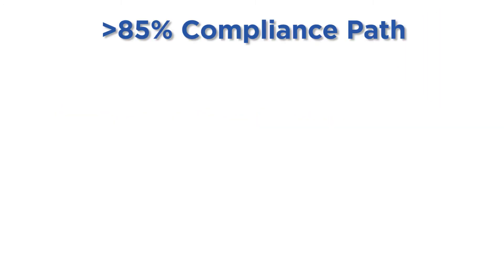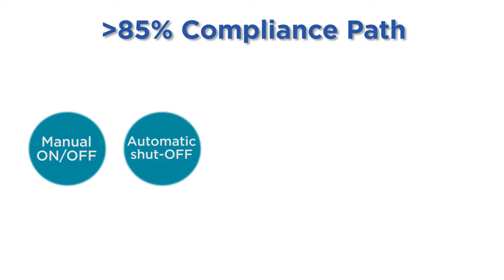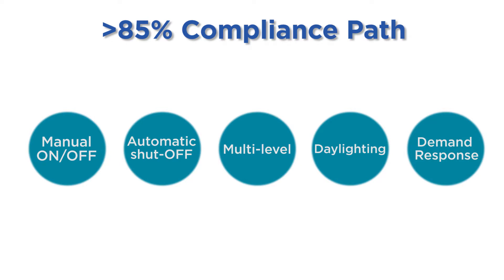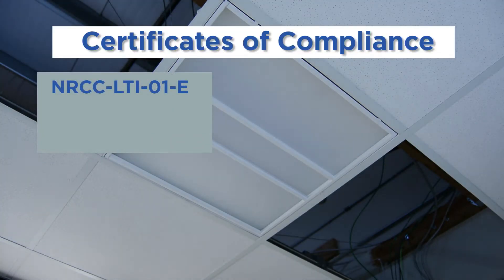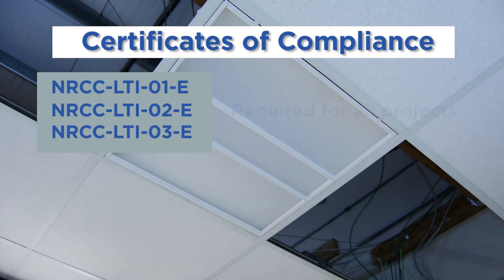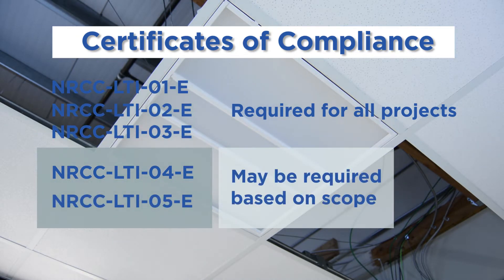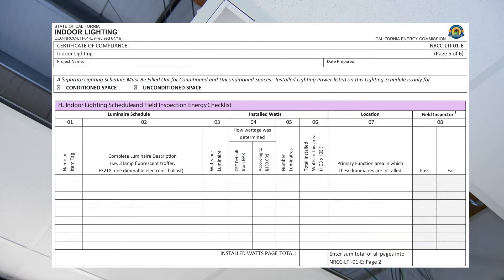Projects using this compliance pathway must include manual on-off controls, automatic shutoff controls, multi-level controls, daylighting controls, and demand response controls, if applicable. Therefore, several compliance forms are needed. Fill out certificate of compliance documents NRCC-LTI-01, LTI-02, and LTI-03 for all projects. LTI-04 and LTI-05 may be required depending on the project scope. Use NRCC-LTI-01 Table H to record information on the replacement luminaires, newly installed luminaires, altered luminaires, and luminaires with component modifications.